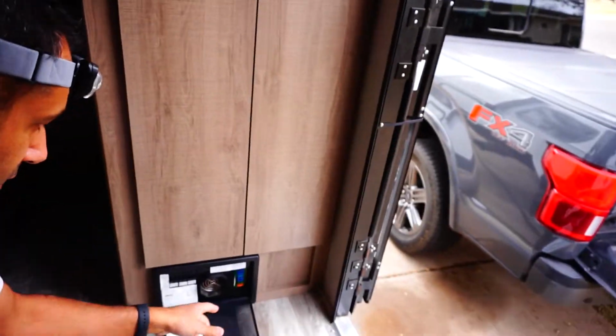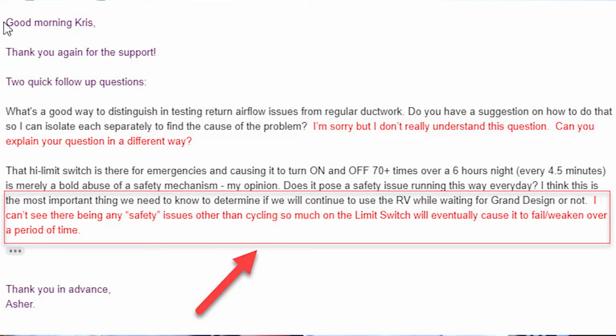There was a tremendous amount of effort trying to troubleshoot why our furnace short cycles, and really no one gave us a straight answer, and I was spending days and nights trying to figure it out myself. I have a technical background. I was pretty much hands-on because I was anxious to get to the bottom of it. So the first conclusion, and the most important, is that there is no safety concern. I personally talked with Eric Sell, and the high limit switch positioned in the back of the furnace is doing what it needs to do in a situation where the chamber gets too hot. And the fact that it happened too frequently has to do with the position of the furnace.